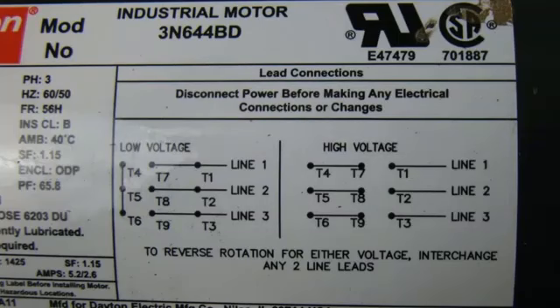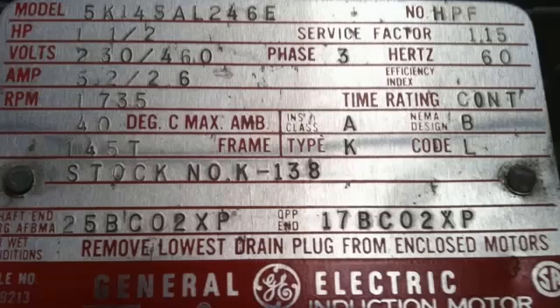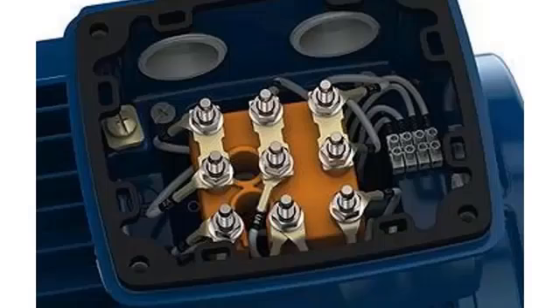All 9-lead connection motors will be wired the same, but you might see them differently depending on the motor. In this instance, we have a picture that's a little bit different. Some nameplates won't always have the picture of how to wire it directly on the motor. Sometimes you have to take the back off and you'll find this, and typically there is some type of connection drawing that would help you know exactly how to wire it for low or high voltage.